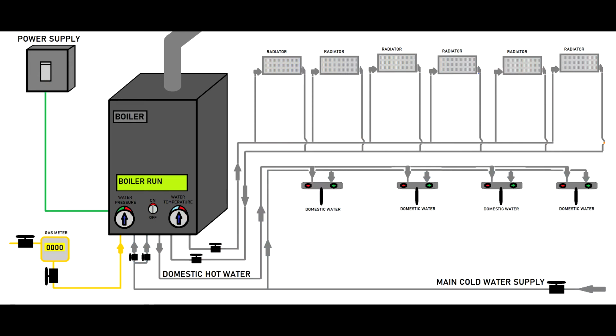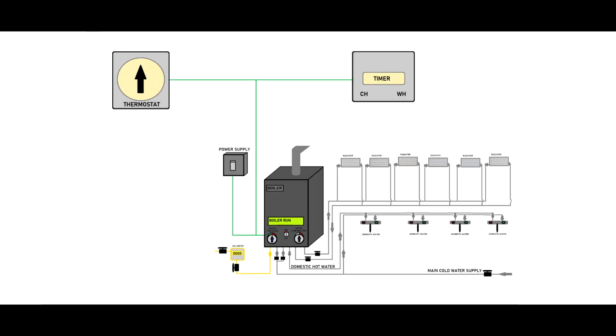It's a Combi one. This is the same boiler as the one I showed you before. But people always want to control the temperature a little bit better. It's not enough to turn on the boiler and rely on the heating agent thermostat which is fitted on the boiler. You need to have a timer and a room thermostat. As you can see, here we have a room thermostat and a timer which has central heating and hot water. You don't necessarily have to use the water heating section of the timer, because this is an instant water heater, and if no one ever turns on the tap, the boiler will never provide hot water.